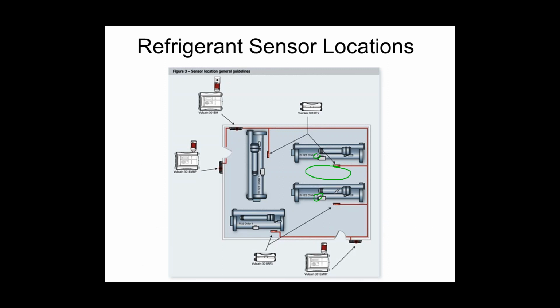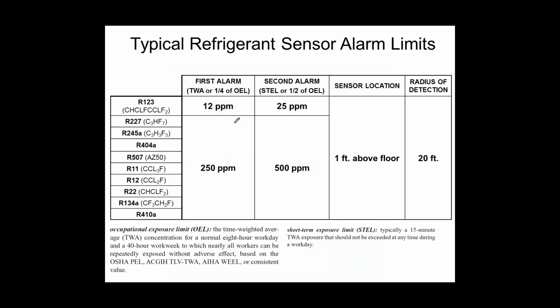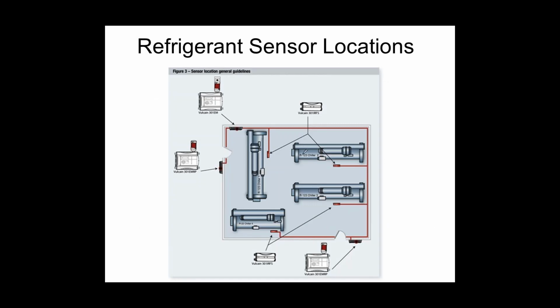We're not going to buy an extra sensor, really. We're not going to do that. And my thought has always been, well, what does this right now say? It's a 123 chiller, which, if you saw on the previous page, had a 12 parts per million limit. But if I change that chiller out to a new one later, it's going to have a different requirement. So maybe I'll end up with a 123 chiller here, but a 134A chiller there. Right? Then I can't do it with one sensor, because typically it's one sensor per gas. So I'm going to have 2 sensors anyway, so I might as well wire it and set it up and put the conduit in for this scenario.